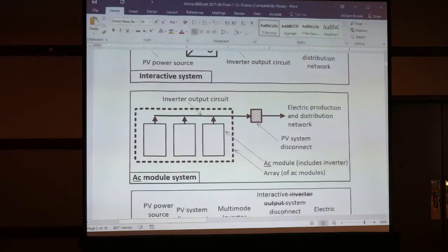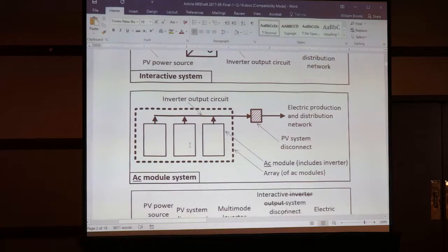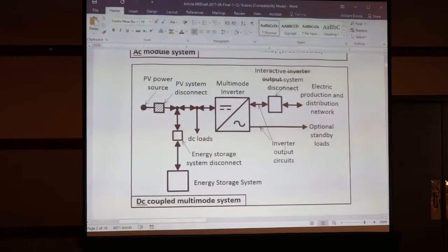Okay. An AC module system. Well, then that's a bunch of AC modules, and there's no batteries in here. As soon as you start interjecting batteries in here, and let's just say this is an Enphase system that has Enphase AC modules in it, that is not going to have any batteries in here. Those batteries are going to be over here. All right, that is on the other side of the PV system disconnecting means.